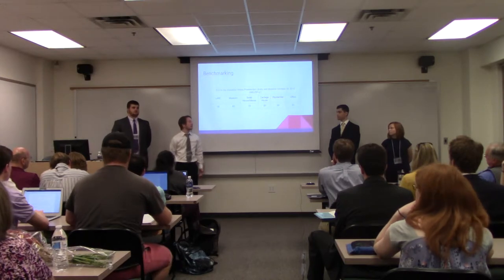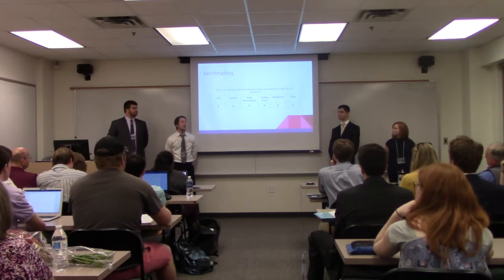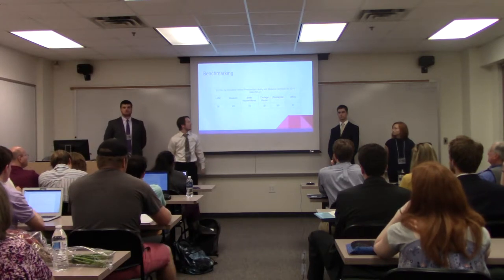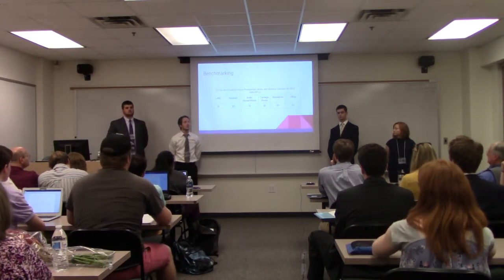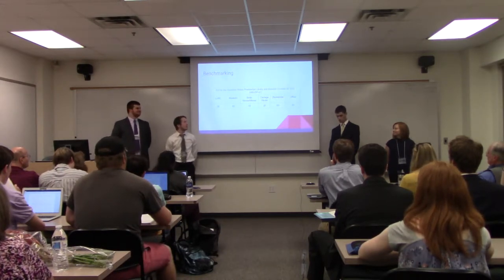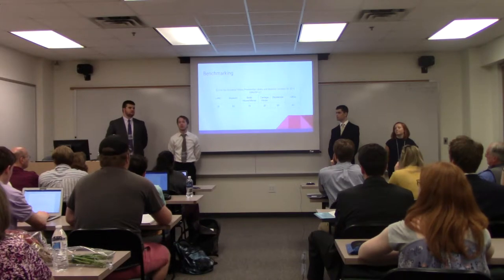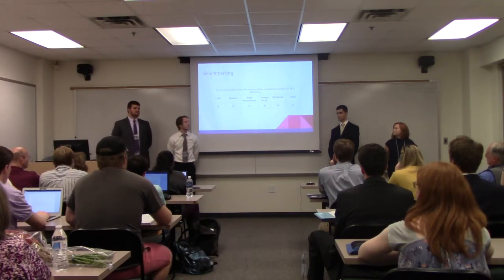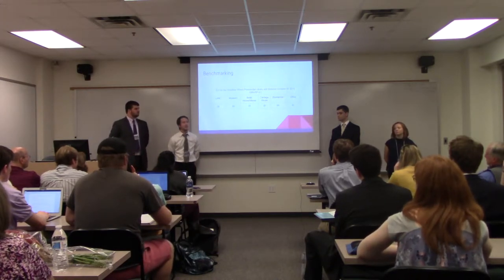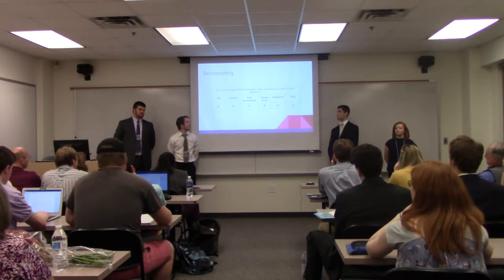For benchmarking, we used the Energy Usage Intensity. The EPA has median measures for residential and office buildings at 69 and 63 kBTU per square foot per year. The museum and the Smith/Manse have fairly similar EUIs to those benchmarks. Since these buildings have all been reconstituted from residential buildings and now serve as museum and office spaces, we thought those were reasonable benchmarks. This basically tells us they have fairly average energy usage, and if they continue to use the utility tracker we provide, they'll be able to see that EUI decline as they implement more energy efficiency tactics.